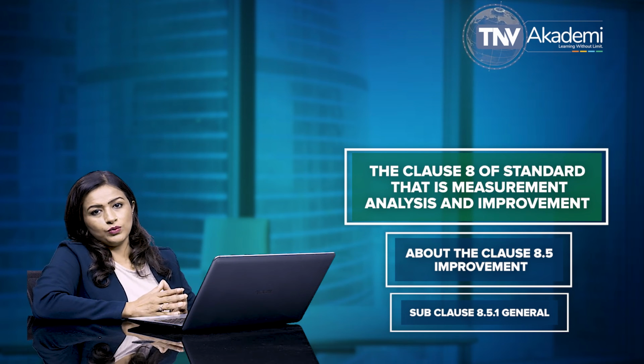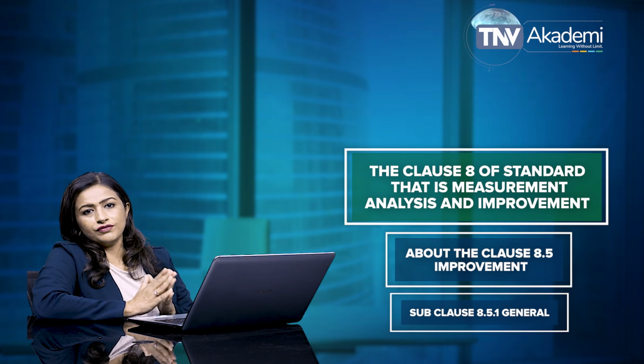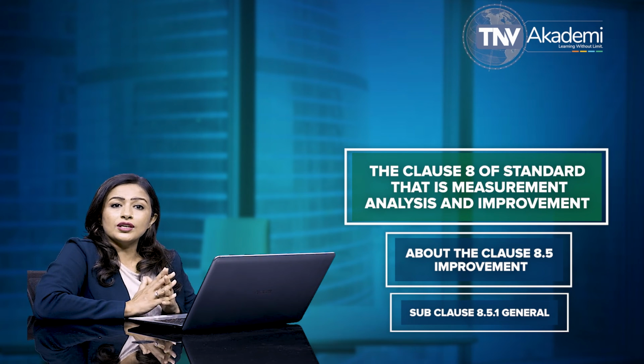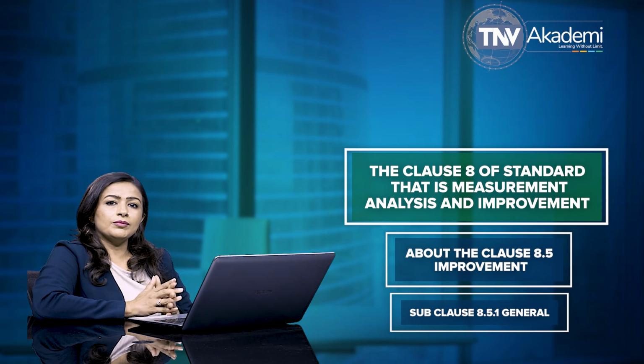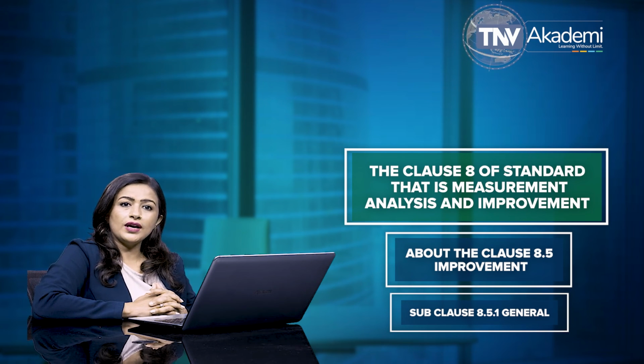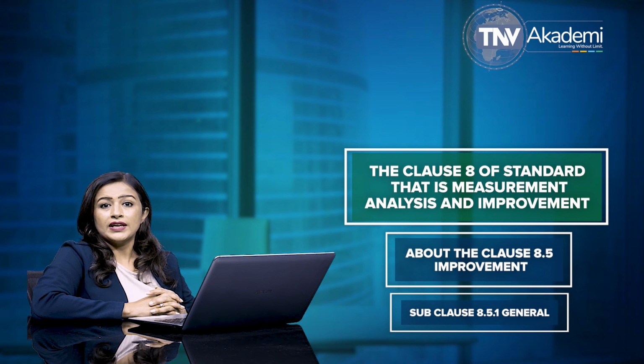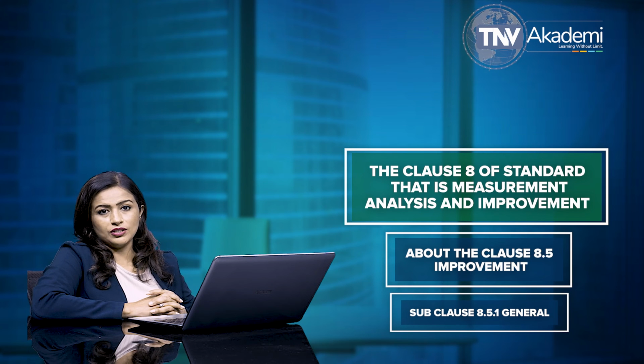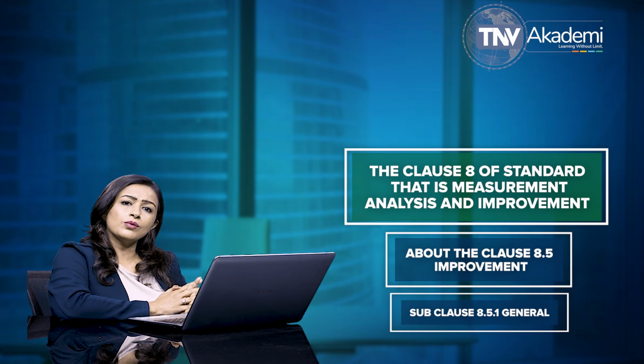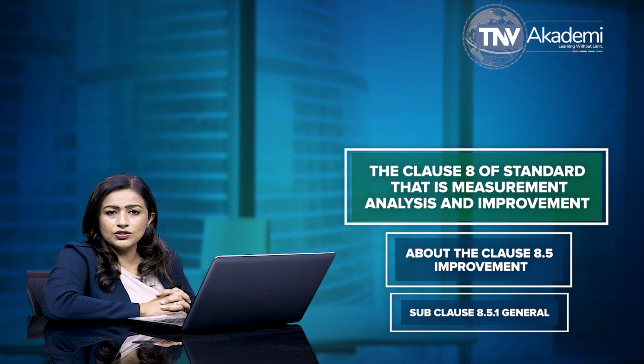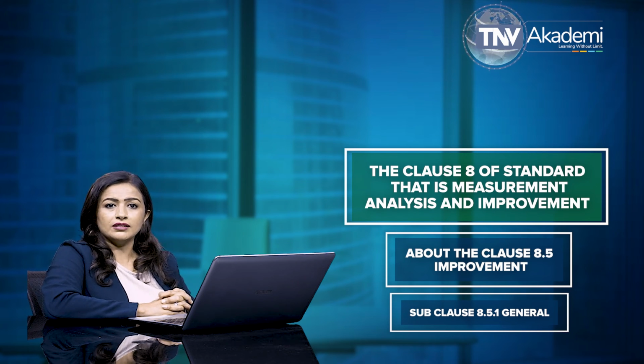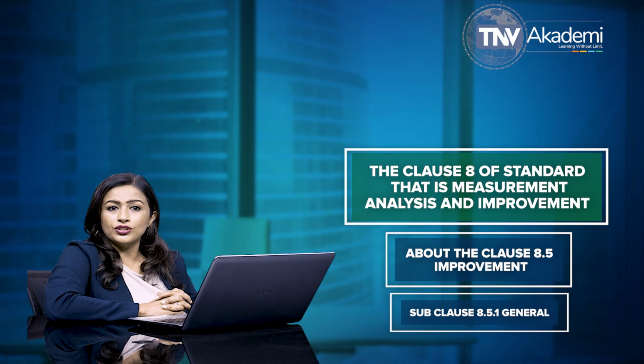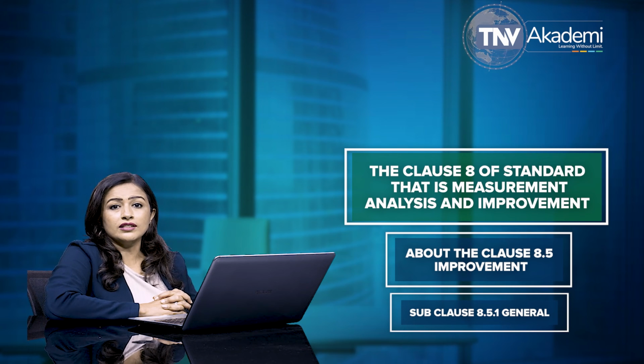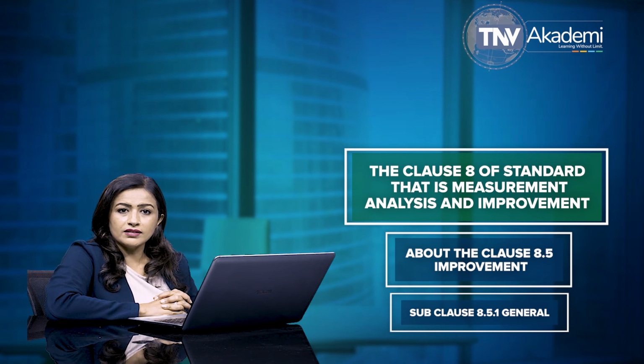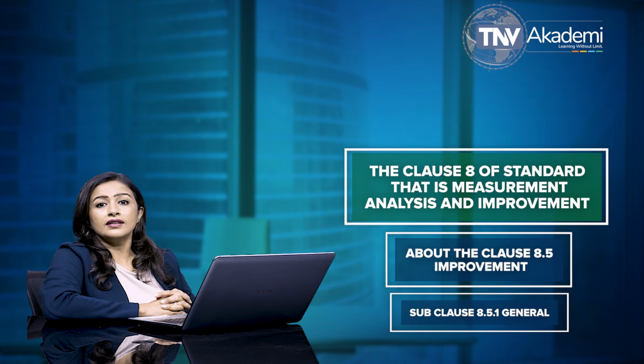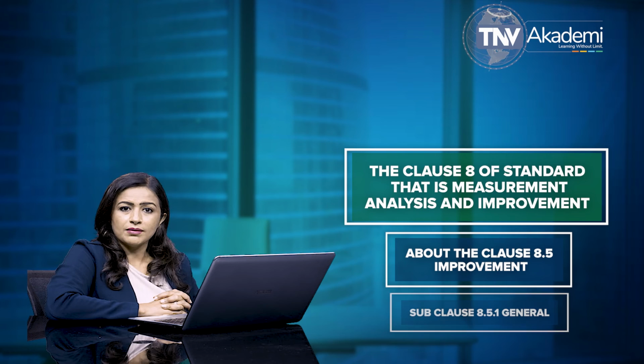Subclause 8.5.1 of ISO 13485 specifies that the organization is required to identify and implement any changes necessary to ensure and maintain the continued suitability, adequacy, and effectiveness of the quality management system. The organization is also required to identify and implement any changes necessary to ensure and maintain medical device safety and performance through the use of the quality policy, quality objectives, audit results, post-market surveillance, analysis of data, corrective actions, preventive actions, and management review.